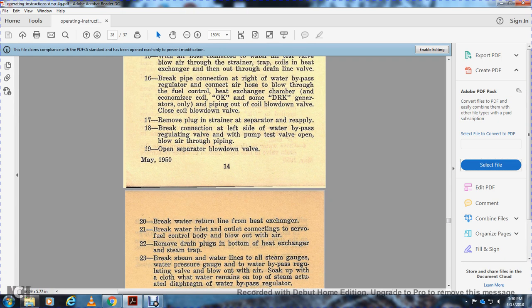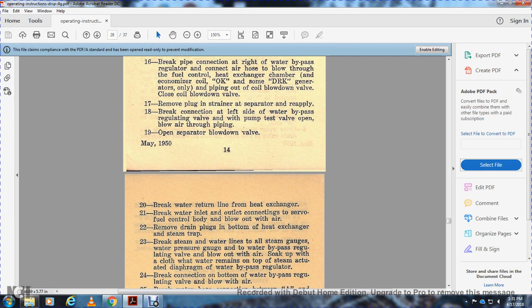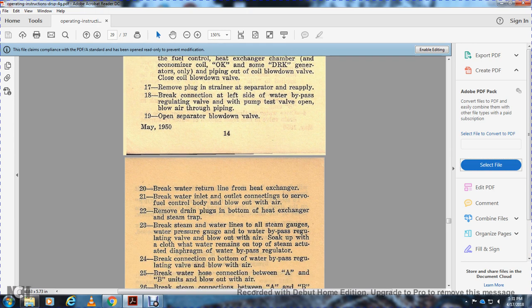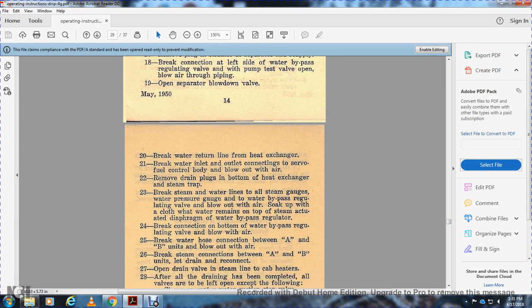23, break the steam water line with the steam gauge, the water pressure gauge for the water bypass regulator valve, and blow out with air. Soak up with a cloth the water that remains on top of the steam actuator diaphragm with the water bypass regulator. 24, break the connection for the bottom with the water bypass regulating valve and blow air with the air. 25, break the water hose connection between the A and B unit and blow out with the air.